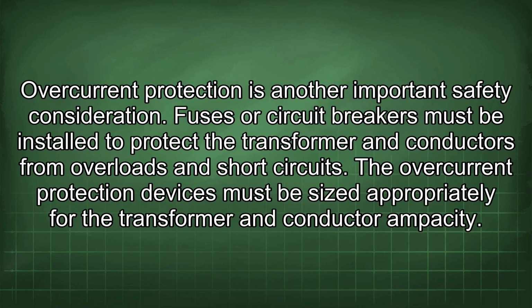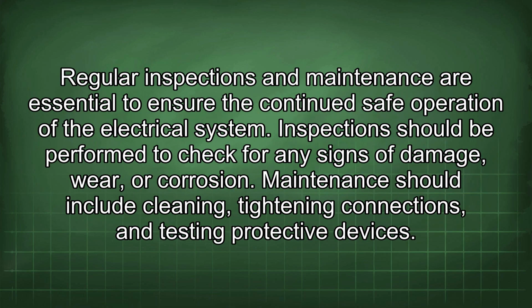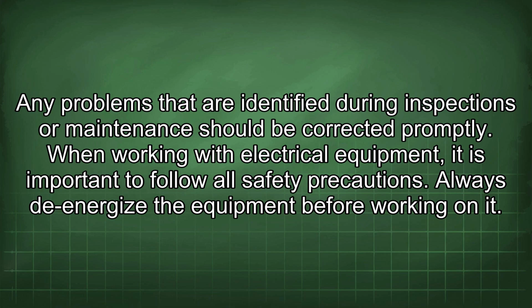Overcurrent protection is another important safety consideration. Fuses or circuit breakers must be installed to protect the transformer and conductors from overloads and short circuits. The overcurrent protection devices must be sized appropriately for the transformer and conductor ampacity. Regular inspections and maintenance are essential to ensure the continued safe operation of the electrical system. Inspections should be performed to check for any signs of damage, wear, or corrosion. Maintenance should include cleaning, tightening connections, and testing protective devices. Any problems that are identified during inspections or maintenance should be corrected promptly.